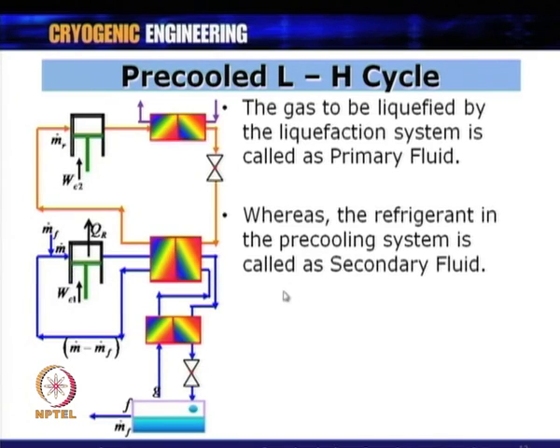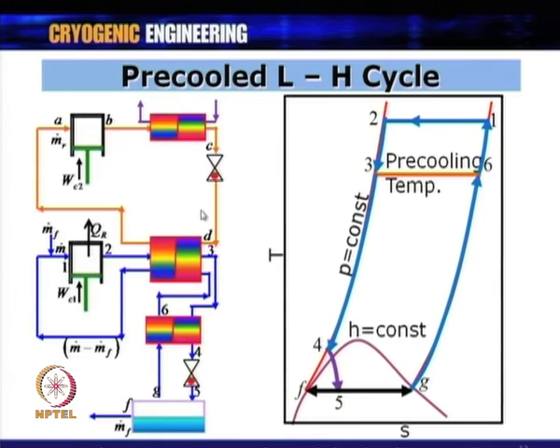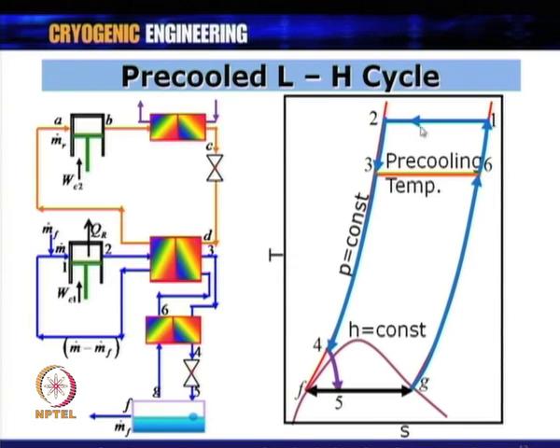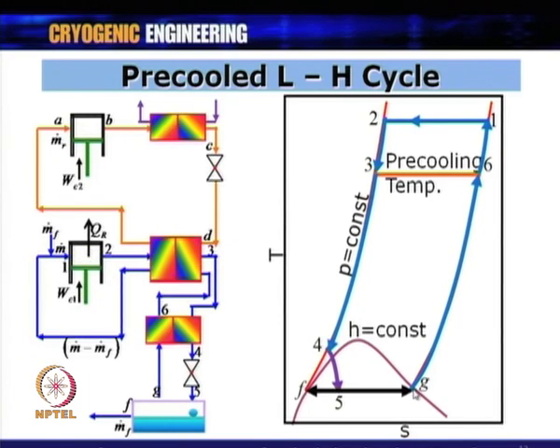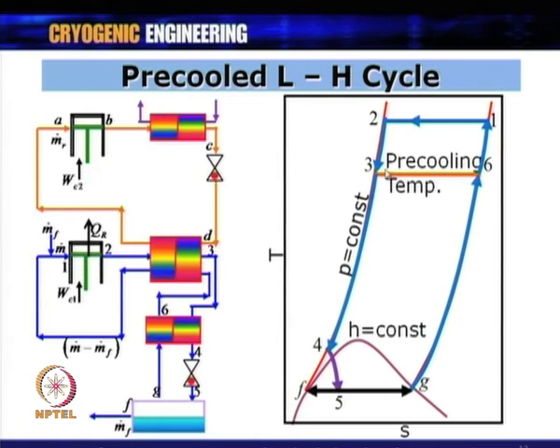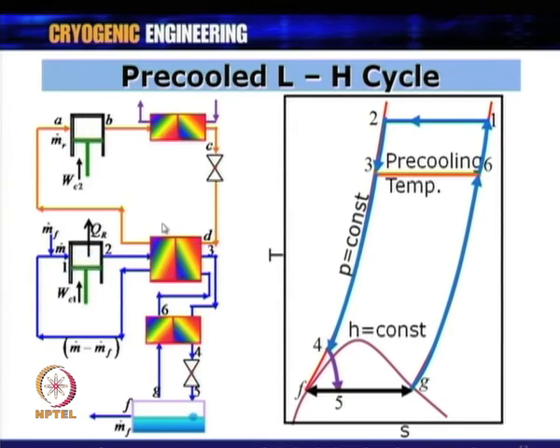On the T-S chart for the pre-cooled Linde-Hampson cycle: process 1→2 is compression, 2→3 is pre-cooling in the three-fluid heat exchanger to the pre-cooling temperature, 3→4 is further cooling in the main heat exchanger, followed by isenthalpic expansion. The return gas goes from G up to point 6, then warms to point 1 in the pre-cooling heat exchanger.